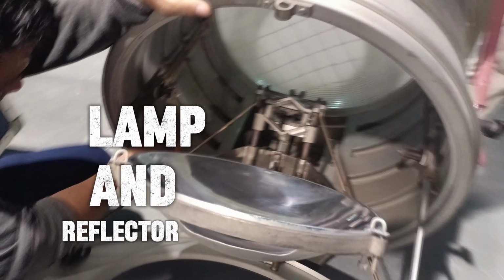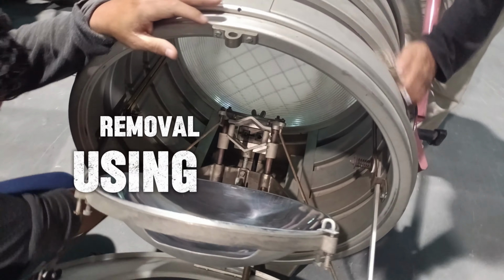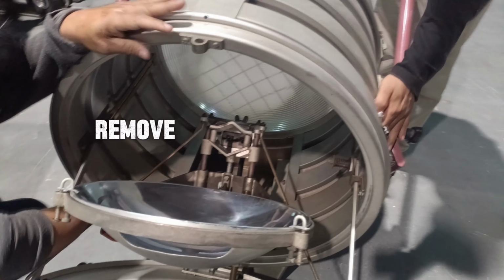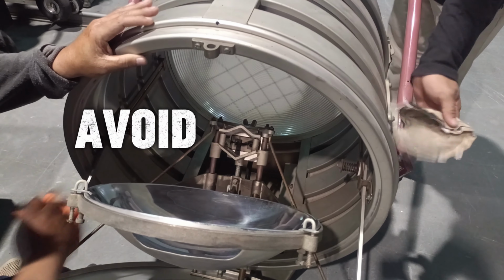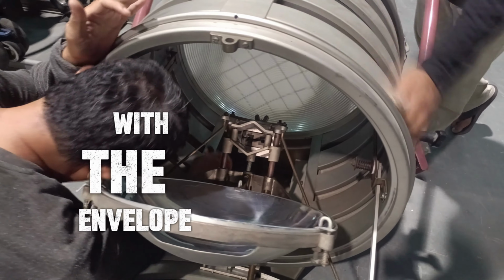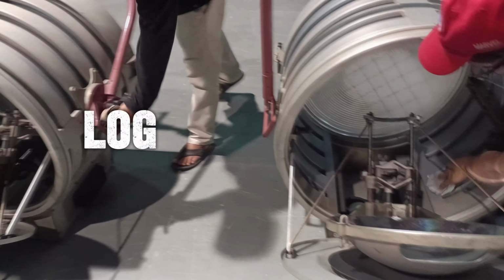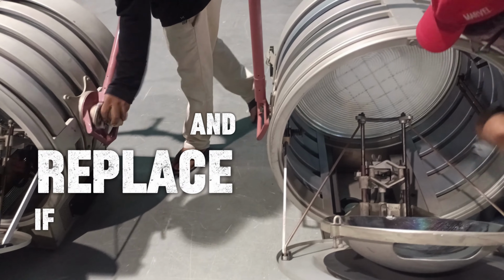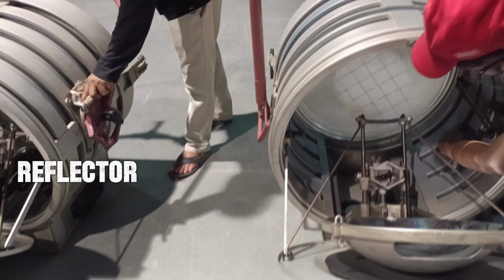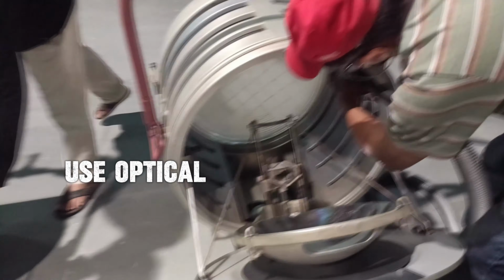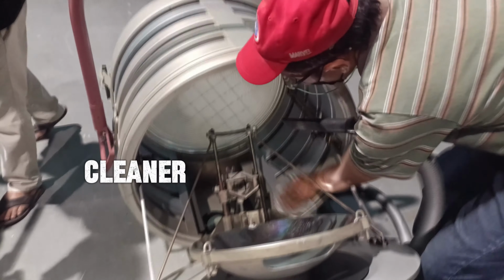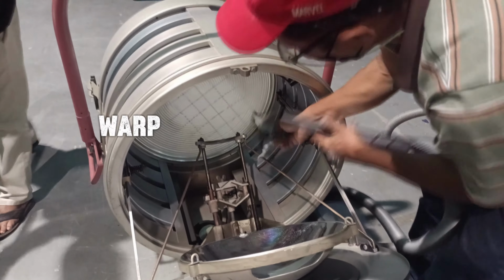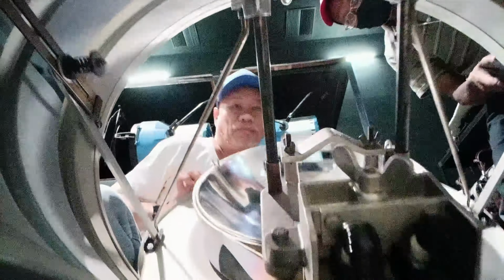Lamp and reflector assembly. Lamp removal: using insulated gloves, remove the quartz lamp. Avoid skin contact with the envelope. Lamp evaluation: check for blackening, arc tracking, or filament distortion. Log burn hours and replace if nearing end of life. Reflector cleaning: use optical wipes and a non-abrasive cleaner. Avoid pressure that could warp the parabolic surface.